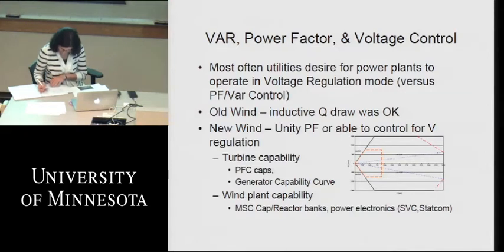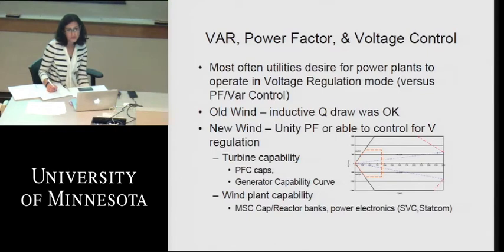In the older days, meaning about 10 years ago and beyond, it was okay to draw inductive power. Well, I should say about 15 years and earlier. 10 years and earlier, if we just did power factor control and didn't draw the VARs from the grid to excite these induction generators, then we could operate as close to unity power factor. We wouldn't be moving the voltage around on the grid, and so that was helpful. It was much better than the older units of 15 years ago. But in the last 10 years, the utilities really want us to operate the whole power plant as much like a conventional generator. So now we've got to have voltage control and voltage regulation.